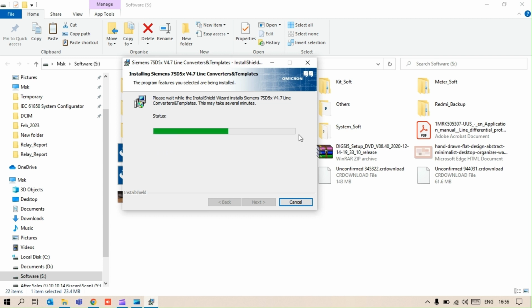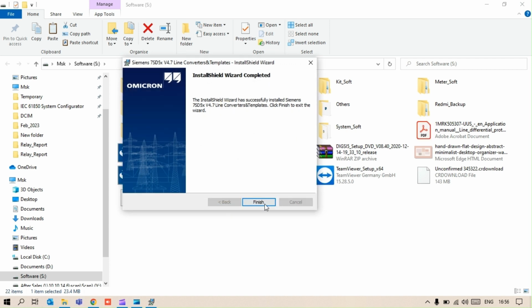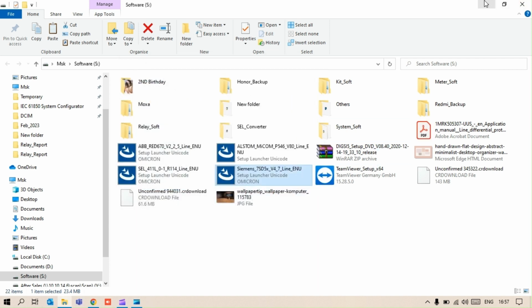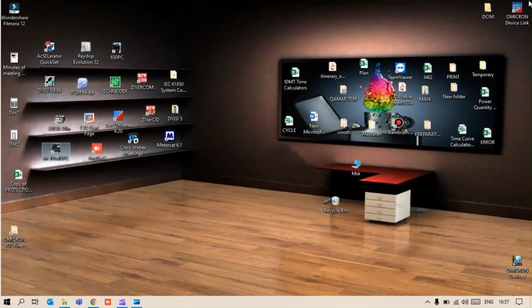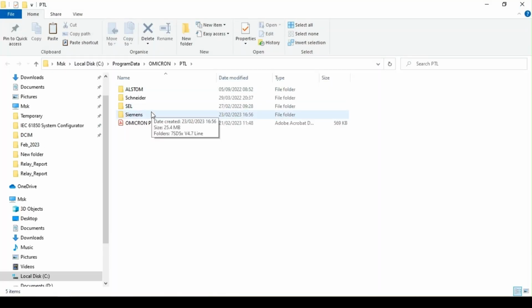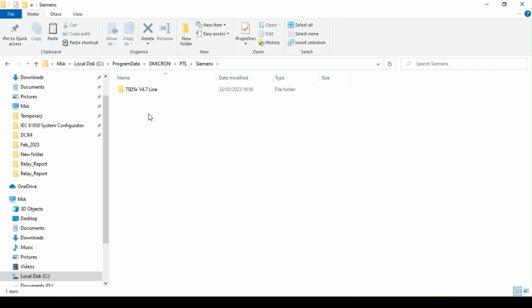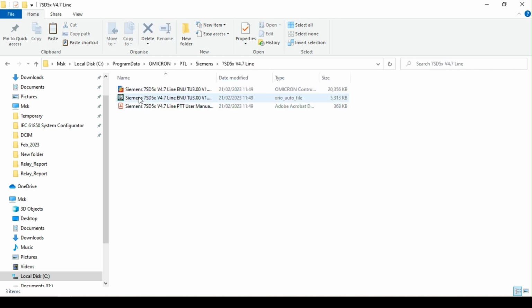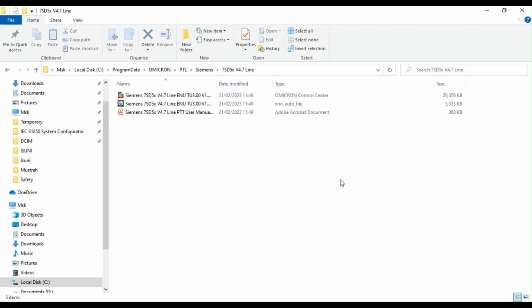With this format we can test everything, even overcurrent, earth fault, distance, differential, power swing, every protection available in the relay. And the other file is XRIO. XRIO we can use for line distance characteristics or timing tests. Even so, we can export XRIO as RIO, and we can use it for testing other devices also, like Freja.